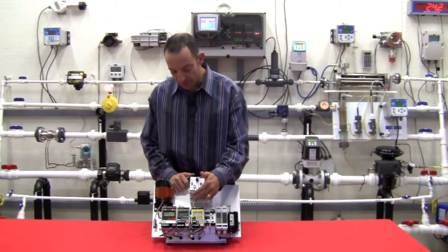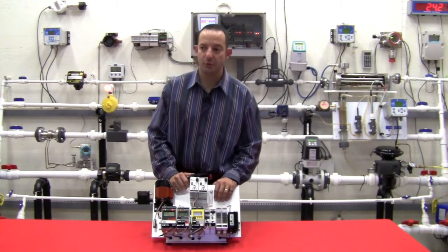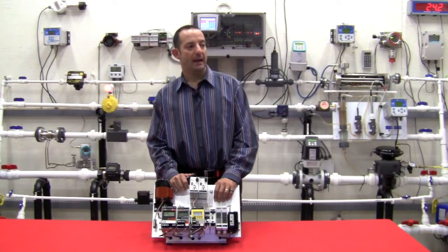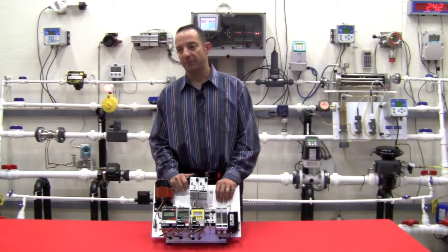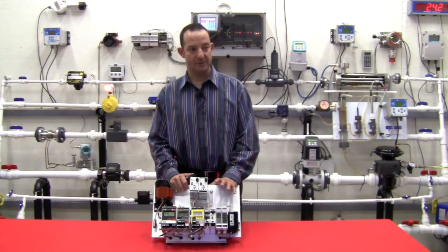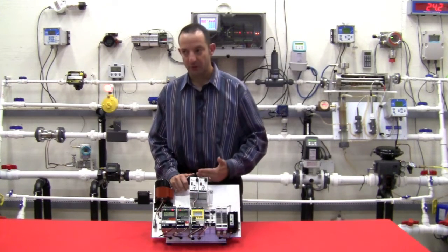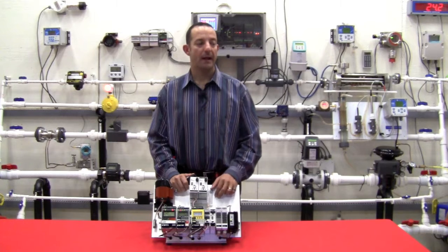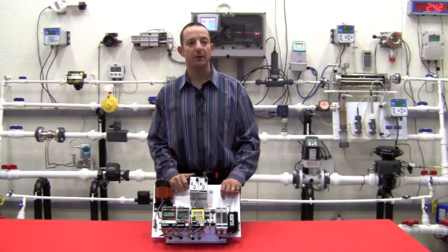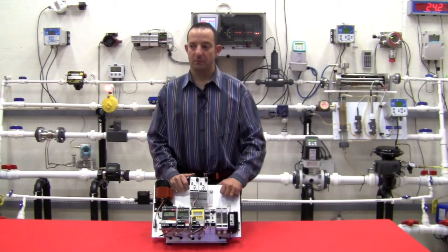Many of the alarm trip units are also available in Class 1 Division 2 or with Class 1 Division 2 approvals as non-incendive for hazardous area installation. And this is a big benefit in field-mounted control panels in chemical plants and refineries and other plants with hazardous environments, because this allows you to locate the alarm trip module closer to the signal source and reduce the length of wire coming from the signal source over to the alarm trip unit. Less likely to be affected by noise and issues of that sort.